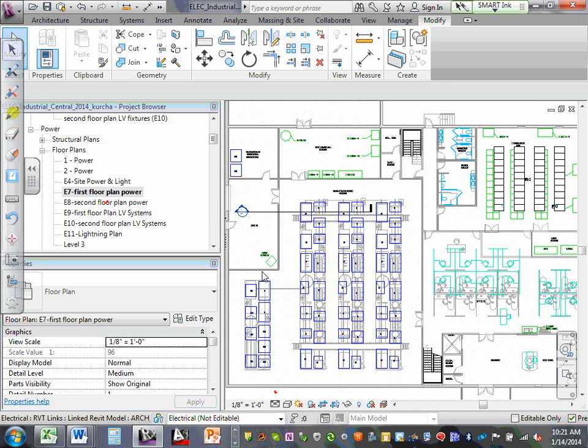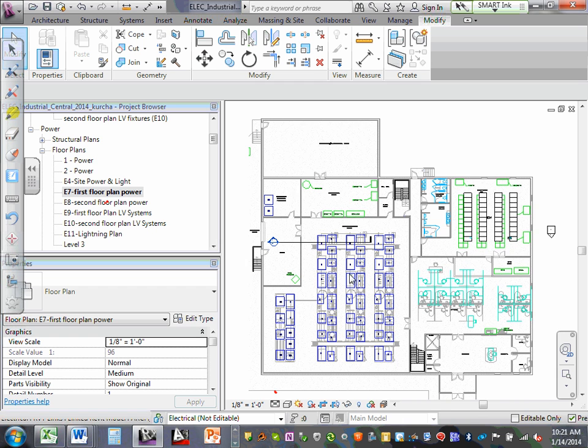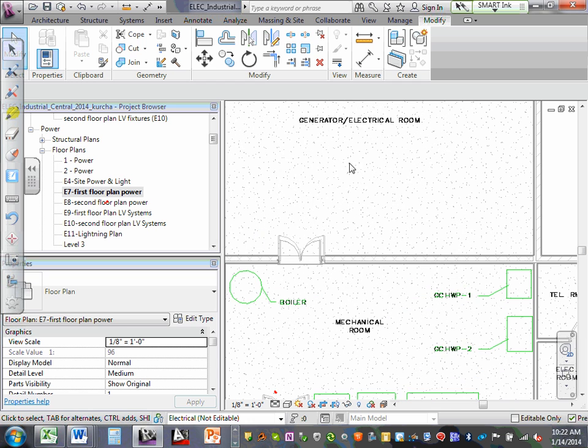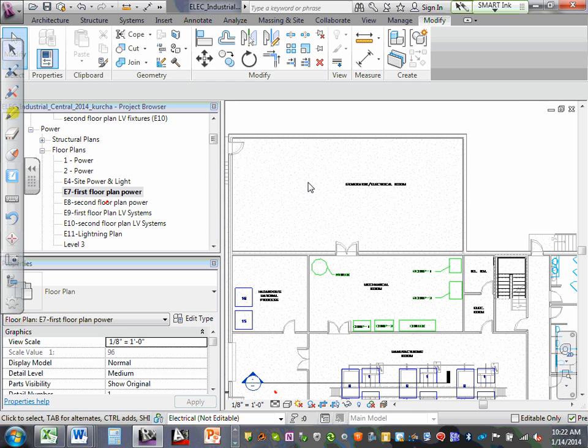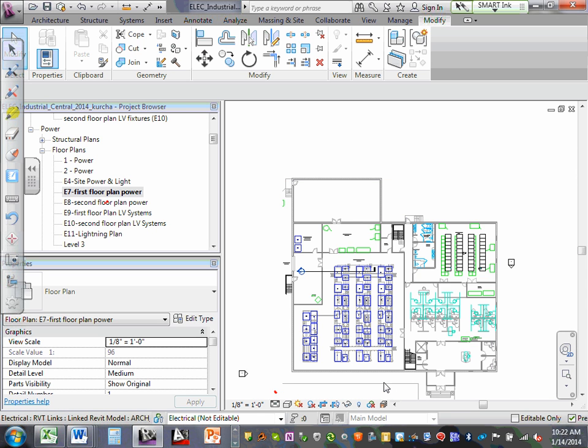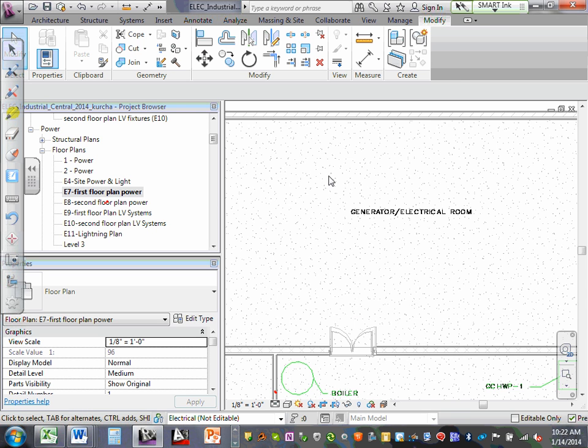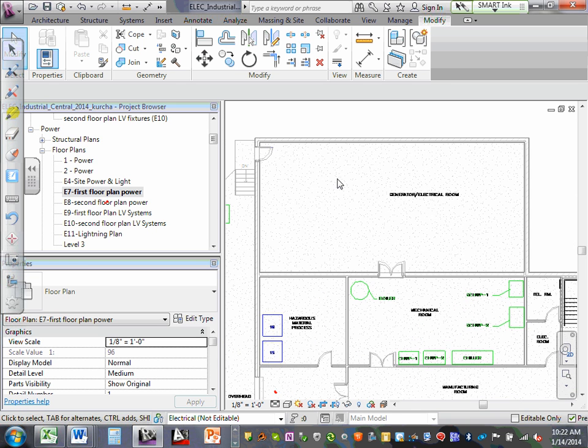So, enclosed offices do not require any notification appliances. Mechanical rooms, any normally unoccupied area, do not require notification appliances. But this mechanical room is pretty big, or generator electrical room. I'd probably put one at the exterior door and probably one at the interior entrance into the room. I'm not worried about ADA or coverage. I just want to get some. And any reviewing authority having jurisdiction that's reviewing the design for permit, we build it, they'll have no issue with that.